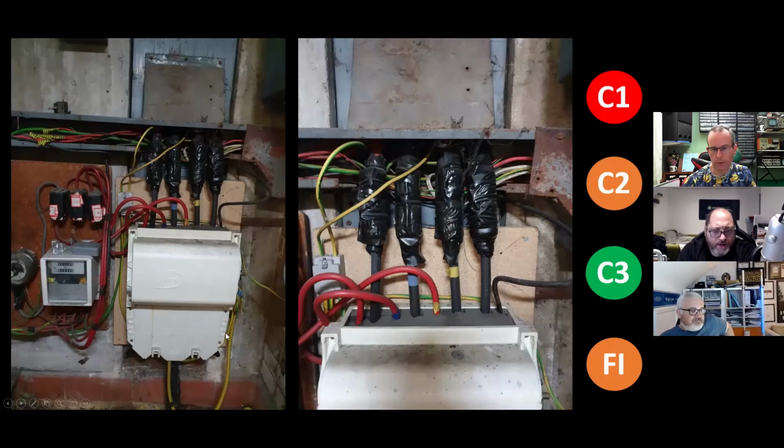Is it TNS? Is it PME? It's been recently done. And considering that they're supposed to be labelling this up, but you and I both know, Dave, the DNOs to this day, their operatives, if they're changing something in the street, they still don't go in and change the supply intake. No. We'll cover that in part 2. Part 2 will have a very specific reason and dynamic around it, because I think we will do it, because we've got some great installation pictures which we can put in.